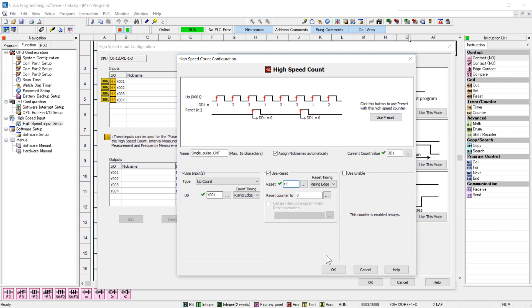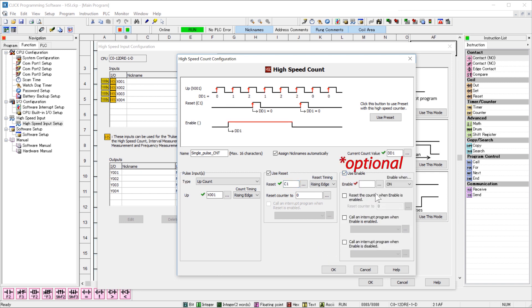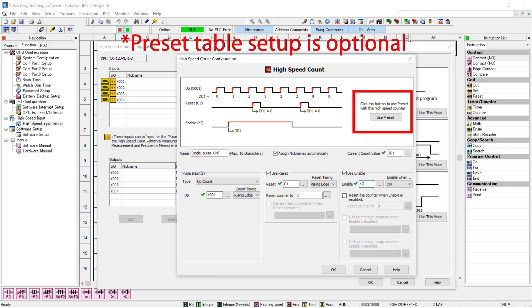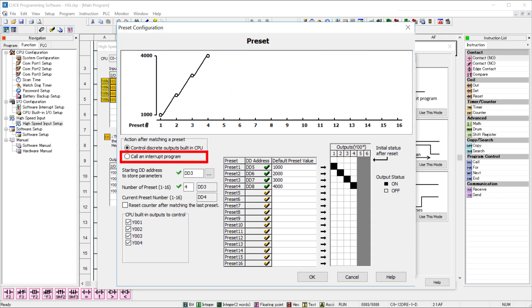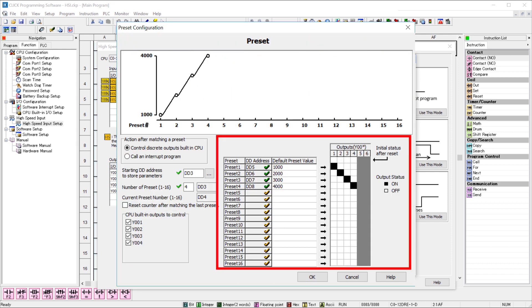The next option allows you to enable or disable the count based upon the status of this bit. You can also define a preset table here. This will turn on or off outputs or call an interrupt program when the count reaches certain values. Now this is completely independent upon the scan time of the CPU and can be very useful in certain high-speed operations.